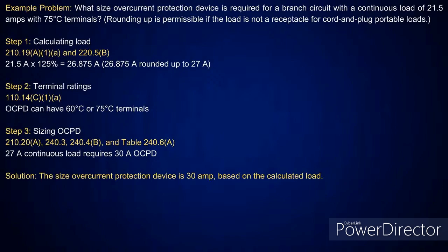Now, the first problem we're going to look at, we're going to size the overcurrent protection device, and this is going to be for a branch circuit with a continuous load of 21.5 amps with 75 degree C terminals. Okay, so if you go look at 210.19(A)(1)(a), we'll size basically the conductor here. Right. Now you take 21.5 amps times 125%, which gives me 26.875 amps.